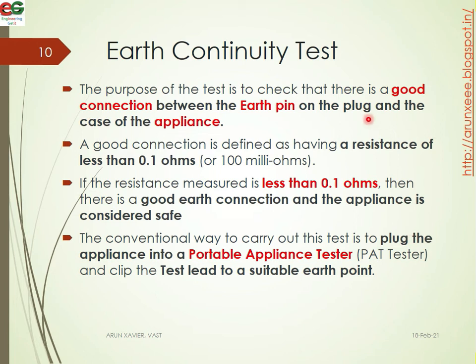The purpose of the earth continuity test is to check that there is good connectivity between the earth pin of the plug and the case of the appliance. A good connection is defined as having a resistance of less than 0.1 ohm (100 milli-ohms). If the resistance measured is less than 0.1 ohm, then there is a good earth connection and the appliance is considered safe. The conventional way to carry out this test is to plug the appliance into a portable appliance tester and clip the test lead to a suitable earth point.